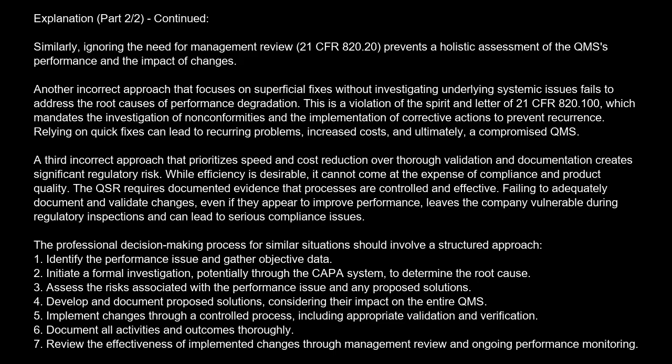A third incorrect approach that prioritizes speed and cost reduction over thorough validation and documentation creates significant regulatory risk. While efficiency is desirable, it cannot come at the expense of compliance and product quality. The QSR requires documented evidence that processes are controlled and effective. Failing to adequately document and validate changes, even if they appear to improve performance, leaves the company vulnerable during regulatory inspections and can lead to serious compliance issues.